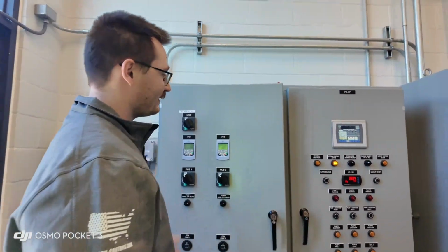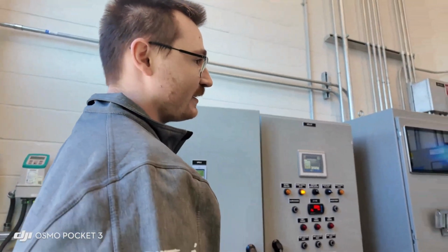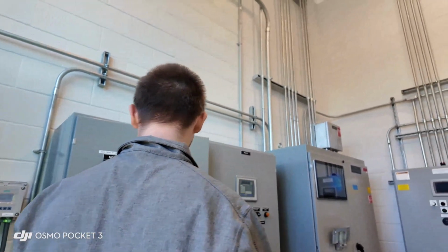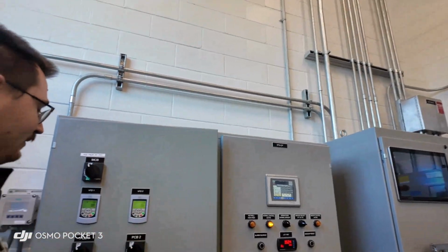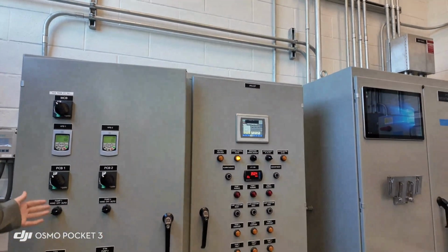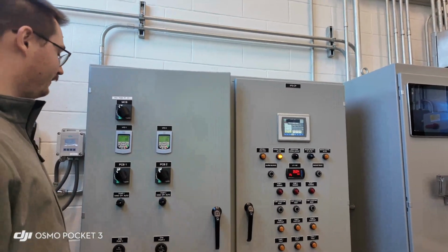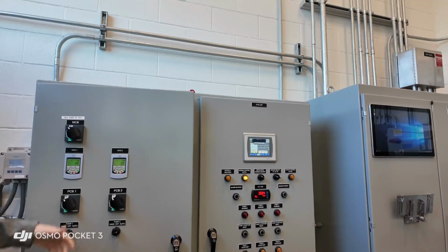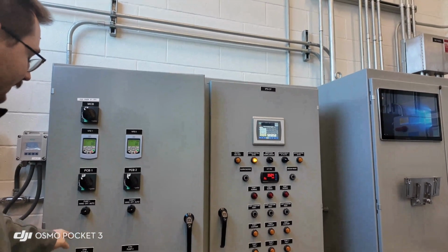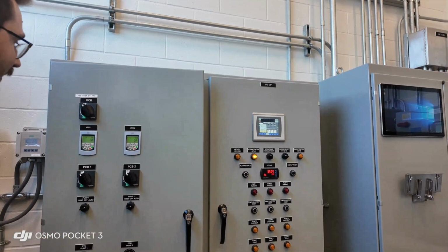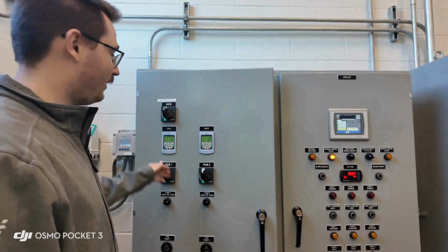Disconnect. It powers the entire panel, and then it goes to a distribution block inside of it and spreads it out to all the devices. The pump 1 breaker and the pump 2 breaker, just like the main breaker, are going to power your first drive and your second drive. These are just HMI keypads that are connected down to these VFDs. So you don't have to open up the panel at all to be able to monitor anything.